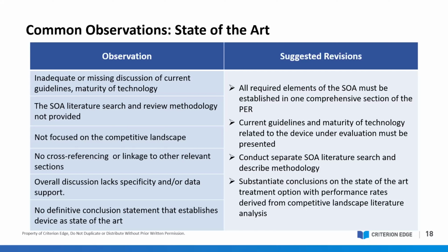So while the APR and the CPR will present data with regards to your device, the SOA is essentially presenting the options for diagnosis, the range of what may be considered acceptable performance within the entire landscape. It's important to ensure that the performance indicators reported for your competitors are aligned with guidelines and professional standards, but also double check early on that these are actually aligned with the performance indicators that you're collecting as part of your post-market surveillance, your internal clinical studies, and your PMPF plan.